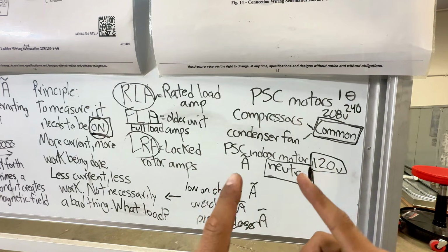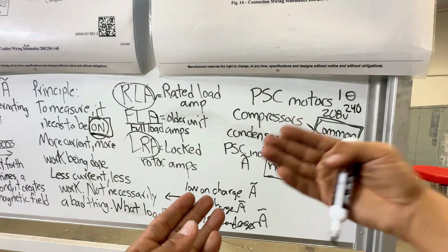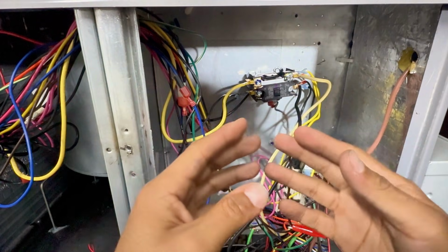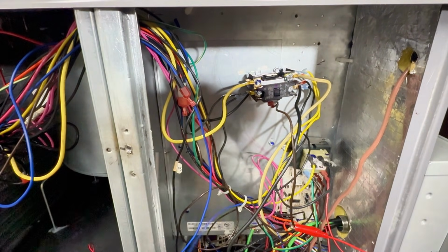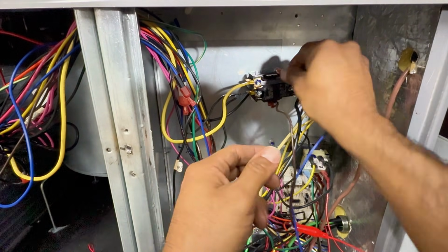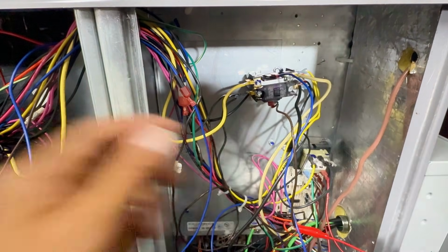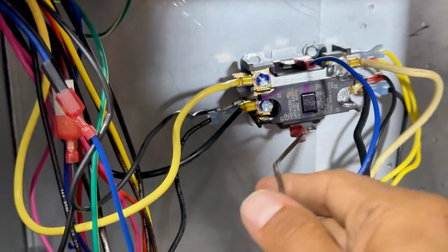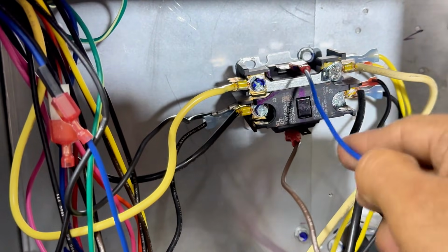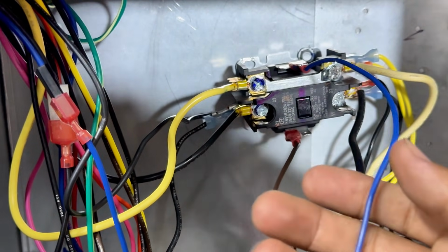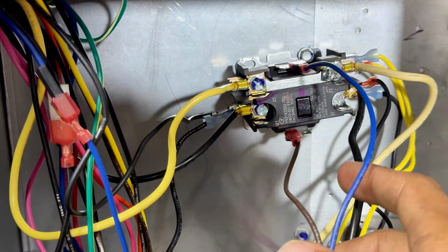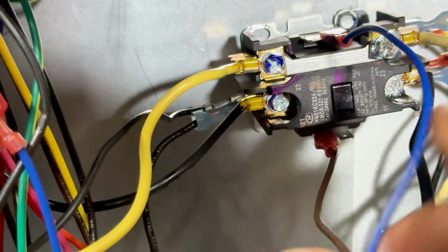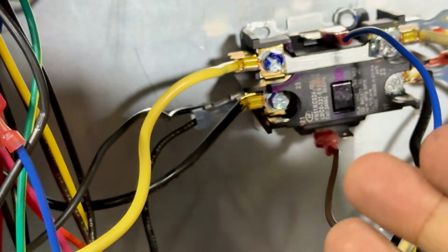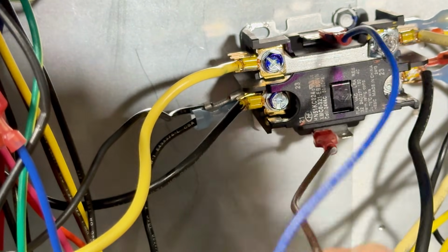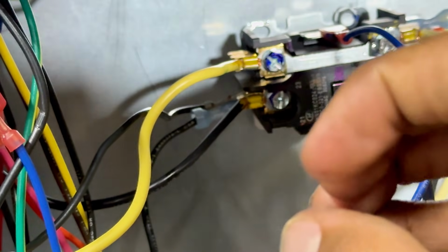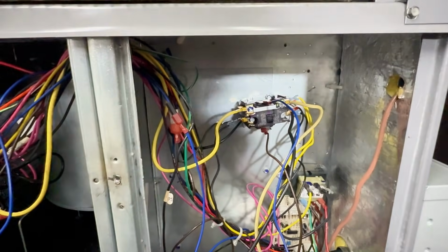So first things first though, we gotta make sure there's power, and then we can measure current. So let's go ahead and check the amp draw of this contactor coil. Normally this is how it would be wired. You have your common, and then your 24 volts, your Y coming from your thermostat essentially. Right now, if you look at it carefully, it's not being pushed in. And if I were to check 24 volts, there's no 24 volts present. So obviously my current would be 0. And I can confirm that, right?